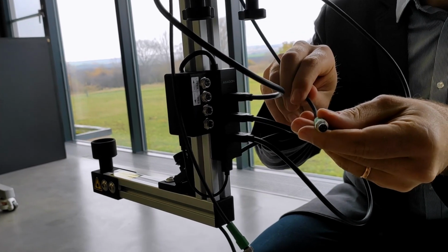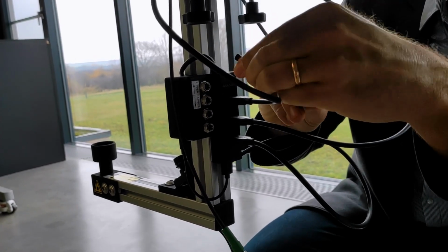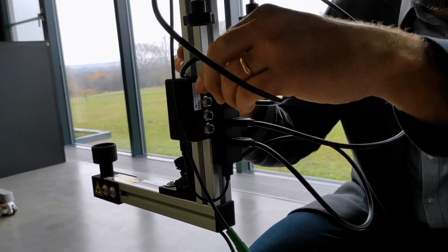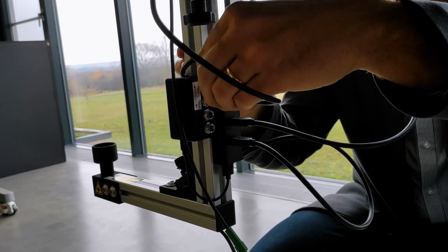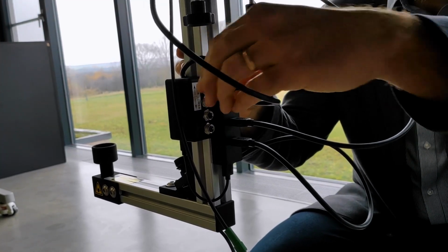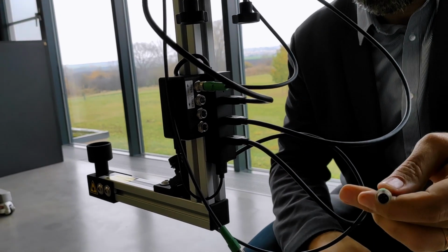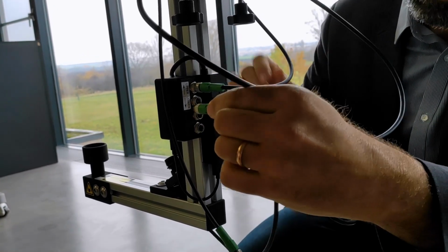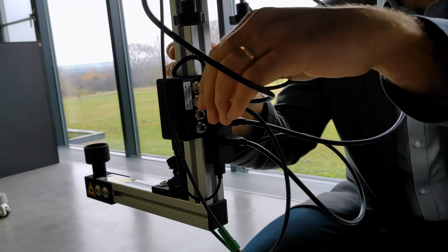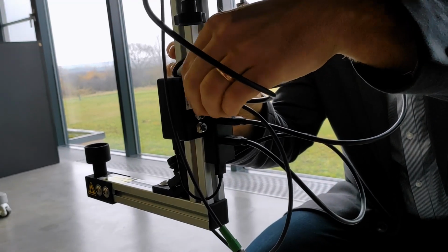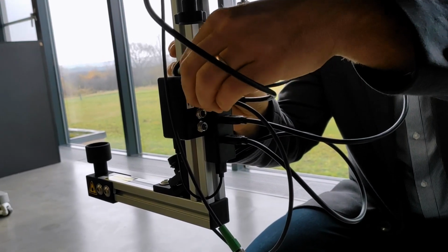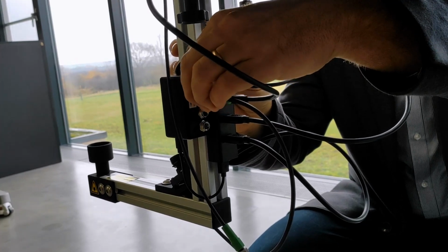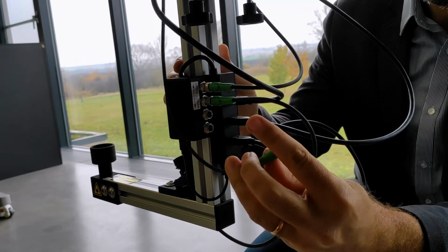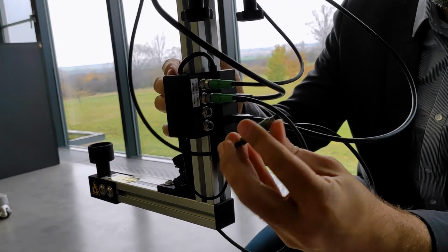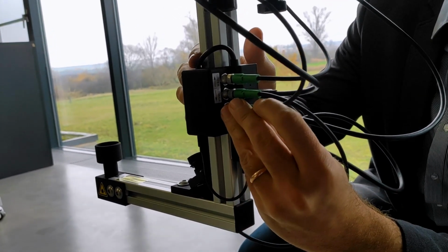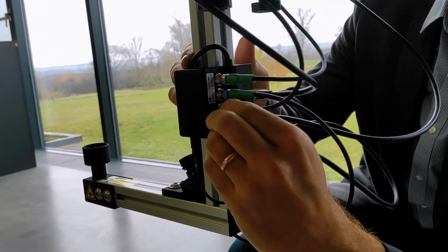Then the power cable of the upper laser projector, which comes from the upper part of the device. Make sure to connect it to the uppermost connector on the control unit on the device, and then the connector of the lower laser projector. Make sure not to switch those around. Then the power connector of the LED light coming from the upper part of the device.